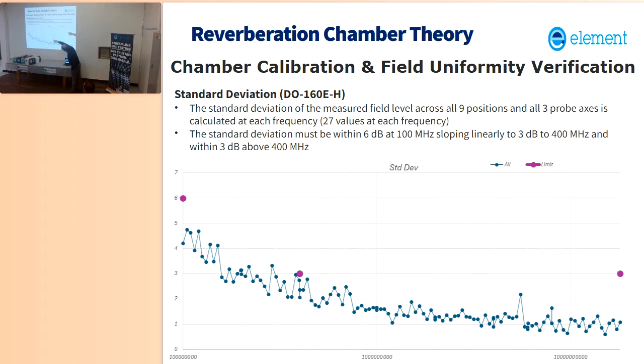And you can see that we got a little bit close right at 400, but we're still meeting the requirement. We're meeting the standard deviation for this chamber from 100 megahertz to 18 gigahertz. And for most of the frequency range up here, it's under 2 for almost all of it, except for this one outlier here. So this is a really good field uniformity. And that's across the whole volume of the chamber. And we got less than 2 dB. And go ahead. Yes, sir.